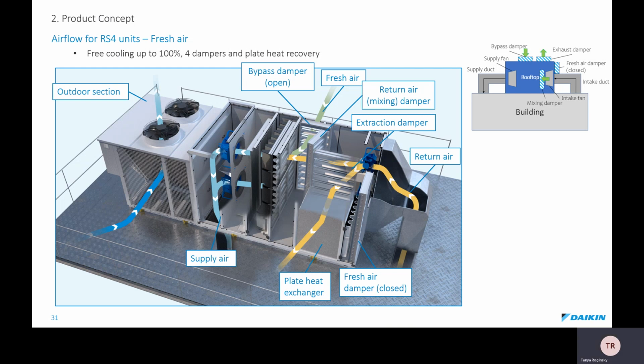On this slide, you can see RS4 unit operation in bypass mode. In the bypass mode, the fresh air damper is completely closed, and the bypass damper, which is also connected to the outdoor air, is open for free cooling. It happens obviously under certain conditions. In this case, the extracted air is going individually through the cross-flow heat exchanger, and no heat recovery is taking place.